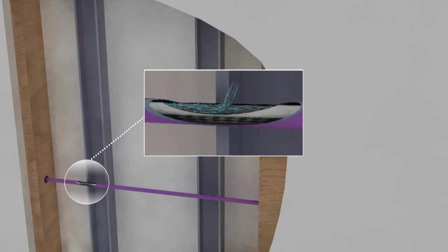Remember, it doesn't matter where the poor termination or compromised wire is. In a wired installation, every device past that compromised wire or bad termination stops communicating when this happens. Worse yet, the problem can start well after the project is completed. With wireless, these problems can be avoided. And when we use a wireless mesh topology, there are multiple paths available to keep the system up and running reliably.